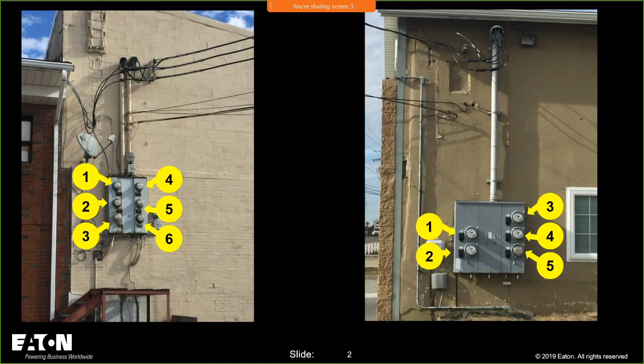All right, let's talk about the 6 disconnect rule. The 6 disconnect rule has been in the National Electrical Code for ages. So what they did in the 2020 cycle was they didn't say that you can't have 6 disconnects. They just said you can't have those 6 disconnects in that same panel board. So what you will no longer see is a panel board with 6 disconnects inside, meeting the 6 disconnect rules, new requirements, and the barrier requirements. You'll probably no longer see that meter center that has 6 disconnects in it, because they're going through the UL standard changes.